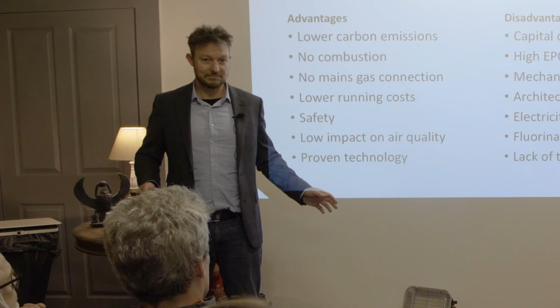The other biggest problem we have is a lack of trained installers. We've had subcontractors come in and put buffer tanks on the outside, which means the heat pump's never going to work. And we've gone to some places where traditional plumbers have plumbed the system as you would radiators, and it's not going to work. So a lot of design and thought needs to go into them.